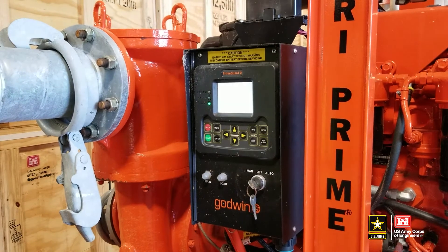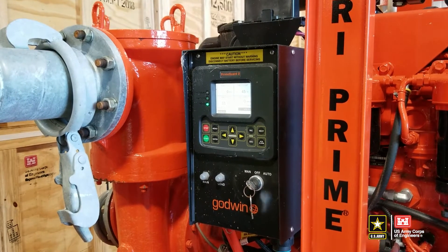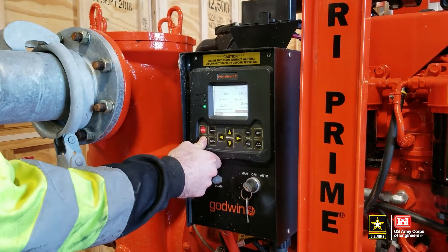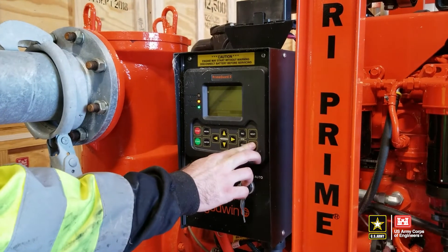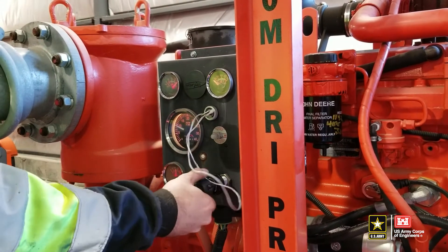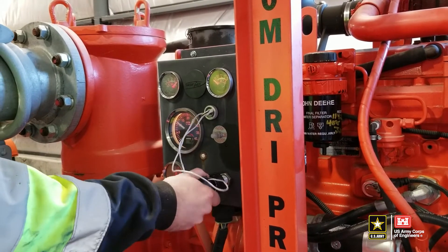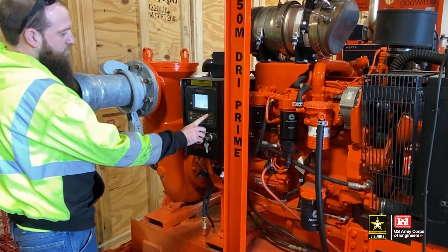Some pumps have a digital control panel and do not have a bypass button. When starting these pumps, turn the key to the MAN setting, then press and hold the green start button to start the engine. Increasing the speed of the engine is done by either turning a throttle dial on pumps with non-digital controls, or using the increase RPM button on the digitally controlled units.